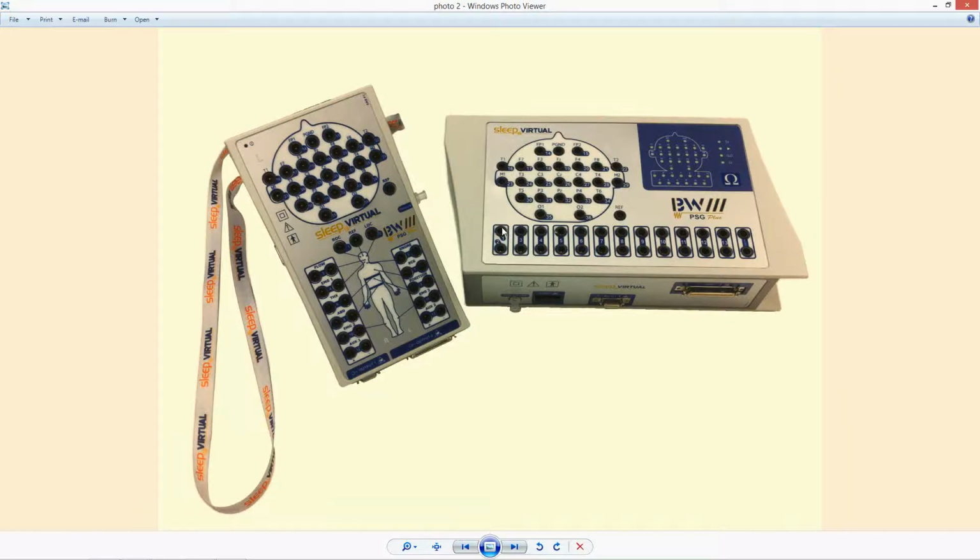has 2 monopolar channels, which are labeled 1 and 2. These are typically used for the eyes, left eye, right eye. And it has a total of 10 bipolar channels, which can be used for the arms, legs, EKG, basically any dual parameter, any bipolar parameter, or for sleep testing as well. We can integrate respiratory channels as well as sensors for polysomnography for sleep studies. The amplifier has a bedside impedance check, so we can check the impedances from the amplifier or from the software.